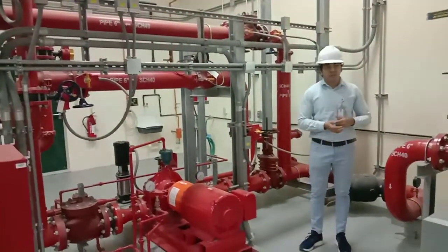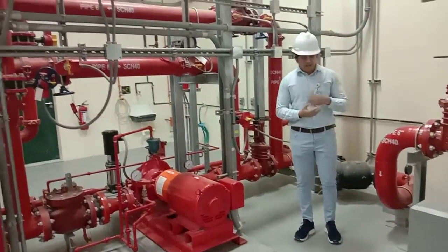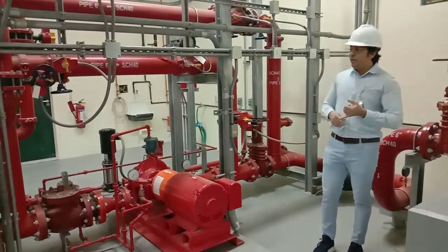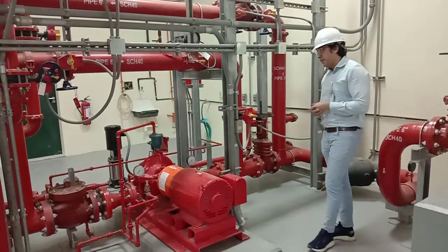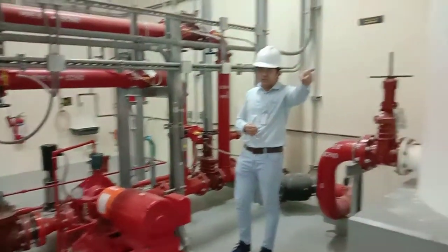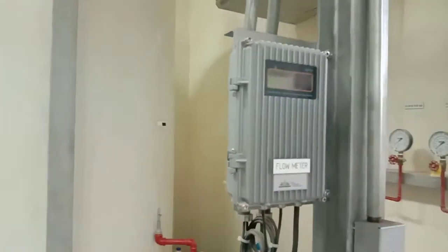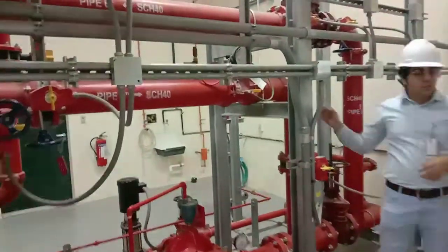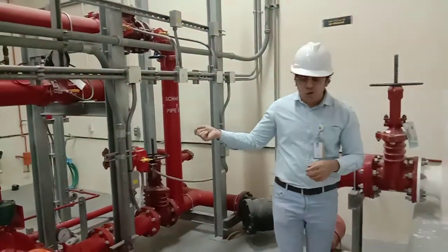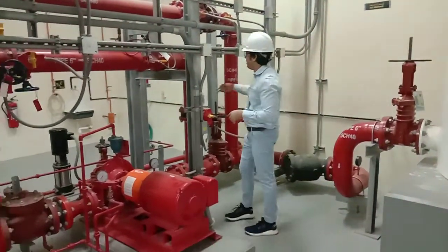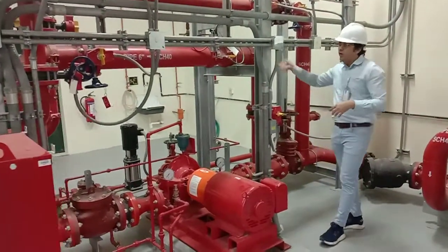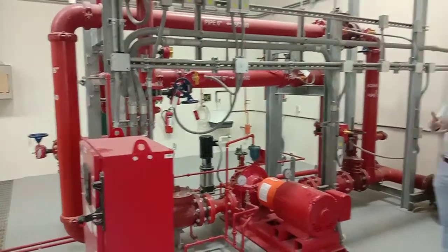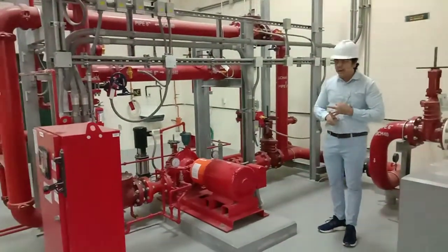Those performance tests we have to do with flow devices. Maybe we can use the test header as well. In NFPA we have three arrangements, right? We might need a test header. We can install flow meters, the one we can see at this end. Or we can use the closed loop metering device, the one I discussed. This closed loop metering device can also be installed in the bypass line. So if you have a bypass line, we can use this device there. So we have three options, right? Closed loop metering device, the test header, and the flow meters.